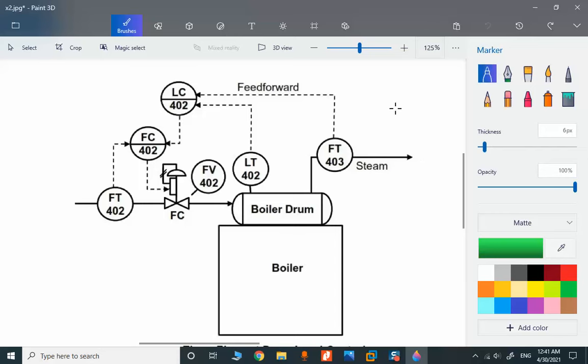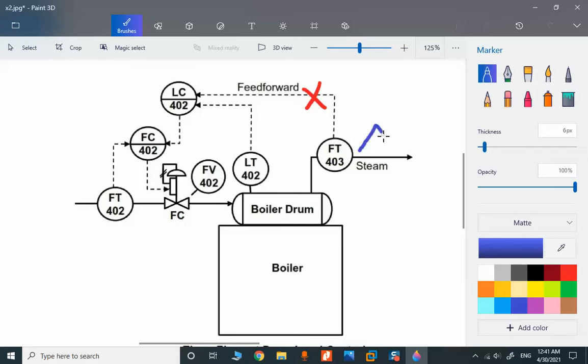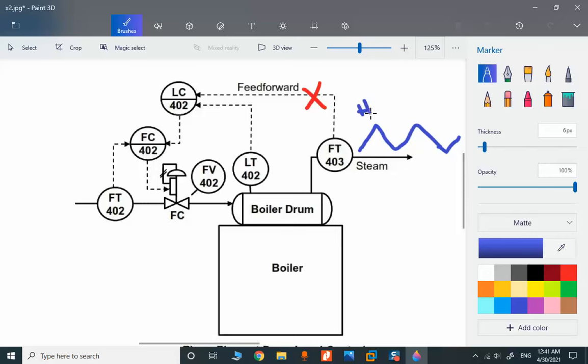If we don't consider the feedforward and any variation in steam is ignored, fluctuation in the steam will have severe effect on the level. When the steam is high, the level of the boiler gets low and it's possible to shut down the boiler. It takes time to compensate and if we cannot compensate, it's possible to shut down the boiler due to low water level.